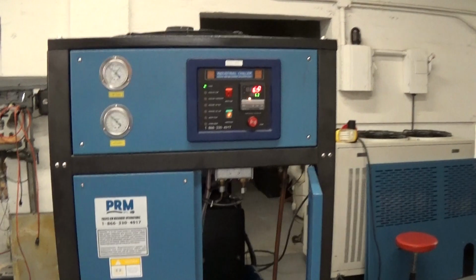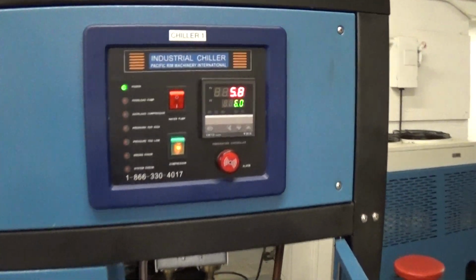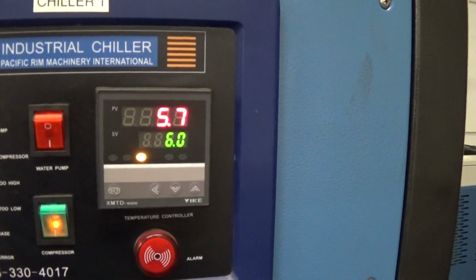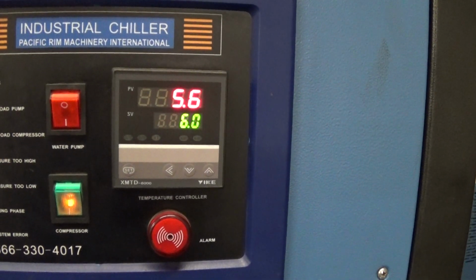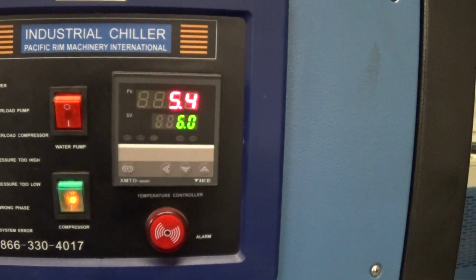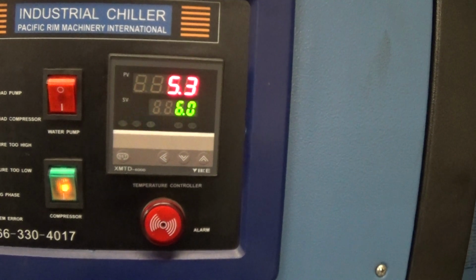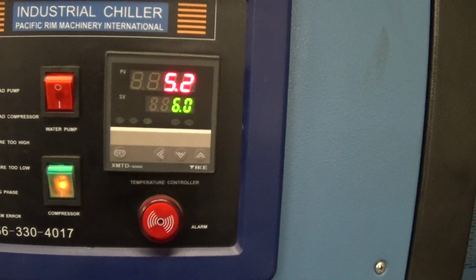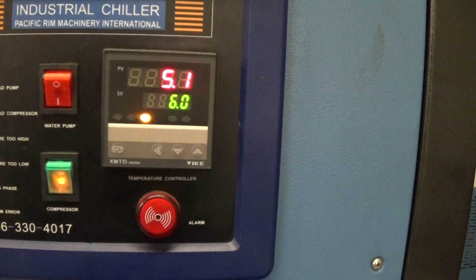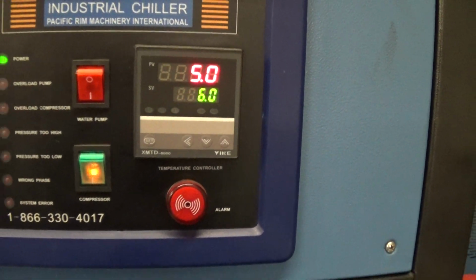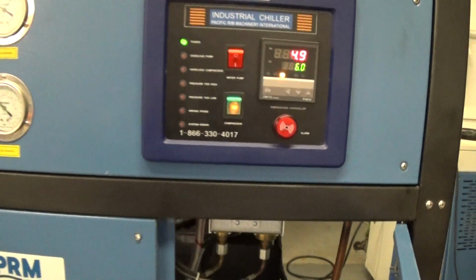So we met our 6C set point. The unit shut off. There'll be a little bit of drift going a little colder, and the differential built into the controller is 1C. So the compressor would turn back on once we get up to 7C. But the pump always runs, of course. So that's it for this one.